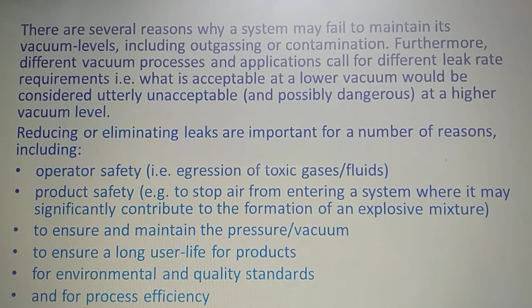Despite all the above reasons, it must be accepted that no system can ever be absolutely vacuum tight. No 100% system exists in nature, so we cannot expect the same in case of vacuum, but still we have to try for a vacuum tight system. It just needs to be manageable, or at least low enough so that the operating pressure, gas balance and ability to reach and maintain a final ultimate pressure are not impacted.